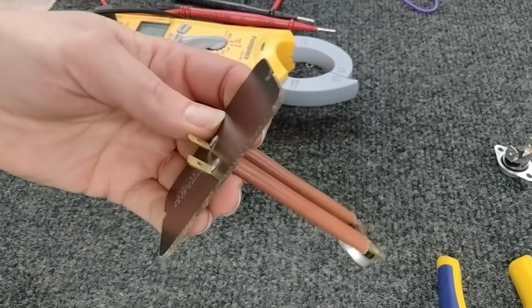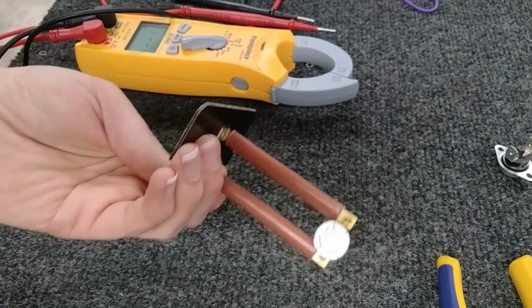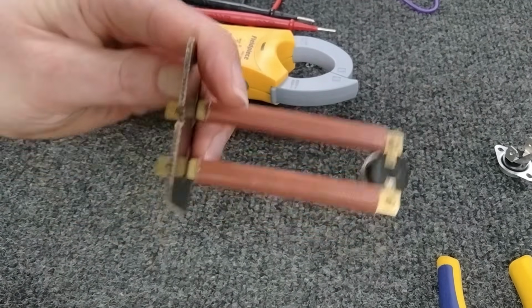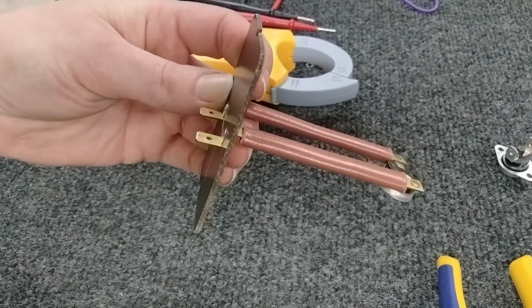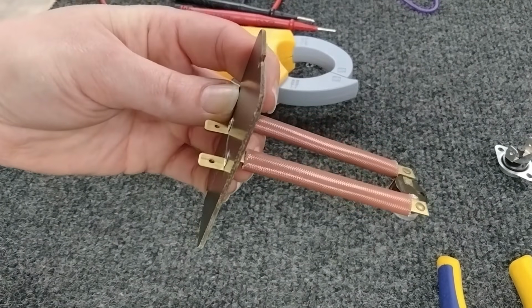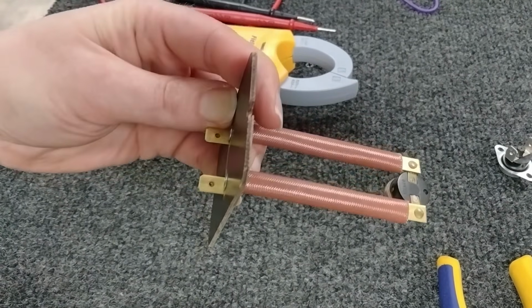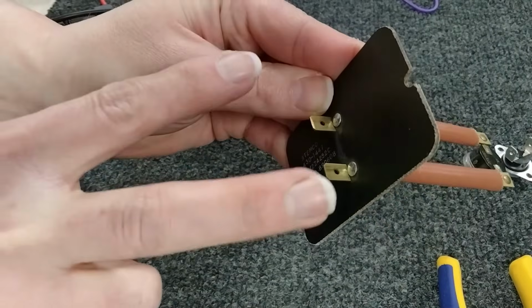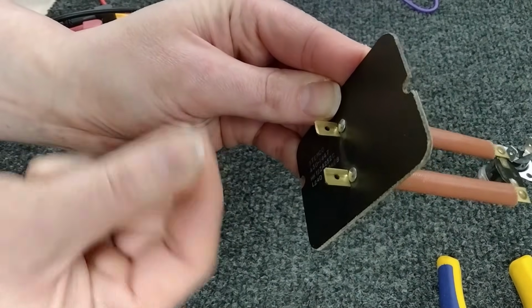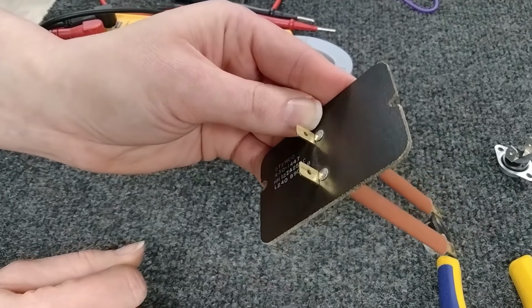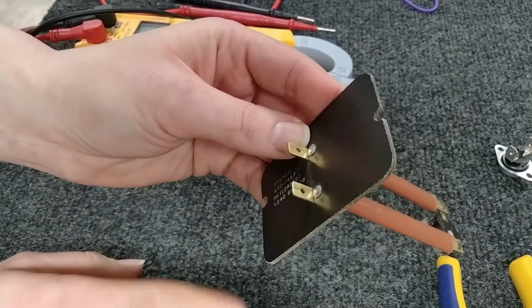Also important to note, a high limit switch can also be doing its job. So when the board gives you a code for high limit, just like the other limits, you're going to take the wires off and jump them together. If it does work just fine, again, do not leave the wires like that.